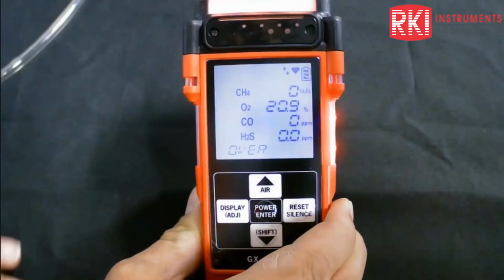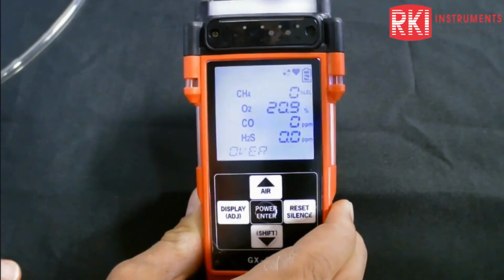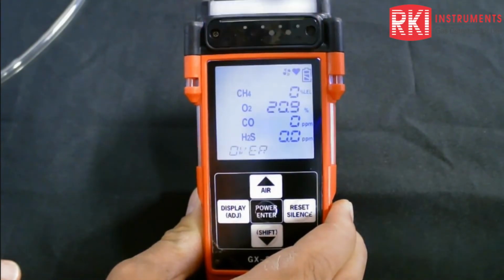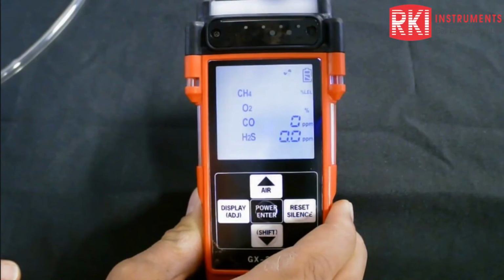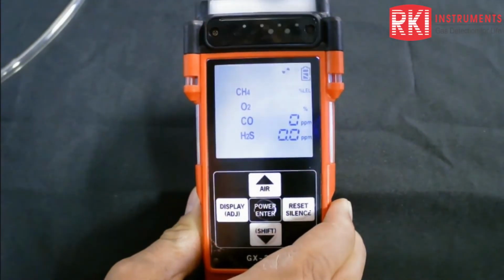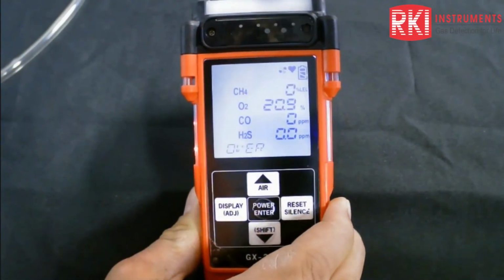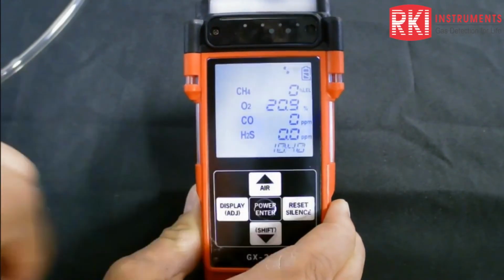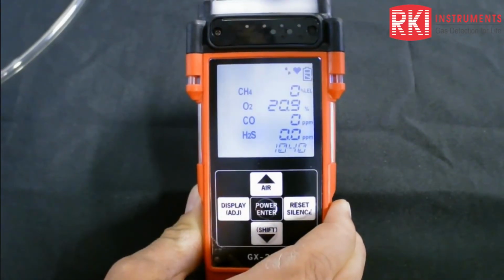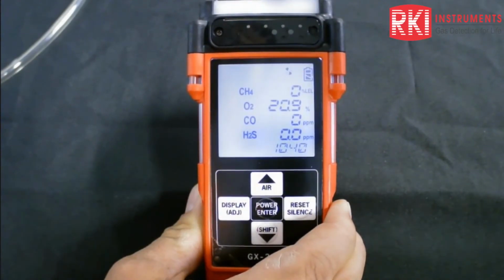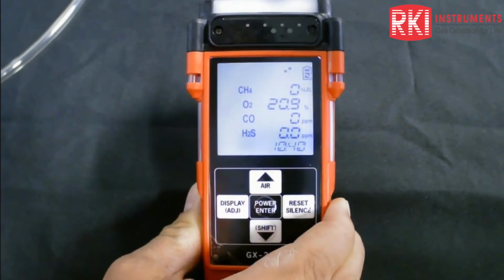But you notice we're still in alarm condition here, even though we're back at normal displays, because the alarms are latching. That's the default, and that way it's a safe way. Somebody's got to acknowledge that the unit is in alarm condition. So if I just press the reset button now again, it clears the visuals out as well. So what we did. Yeah, go ahead, John.